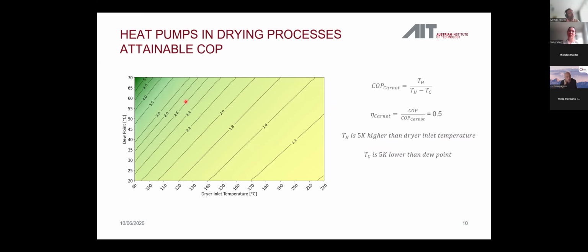So an important question is now what COP could be achieved using a heat pump in the drying process. And we try to get a first estimation using the Carnot approach. So Carnot COP just depends on the temperature levels in the heat pump, where we have the hot temperature, which is on the sink side, and the cold temperature on the source side. Of course, in a real-life heat pump, you would not achieve the ideal COP of the Carnot process. So you would have a certain efficiency, Carnot efficiency, which we assume to be 0.5.